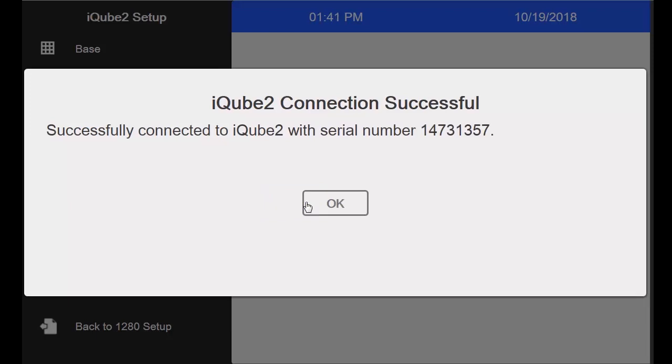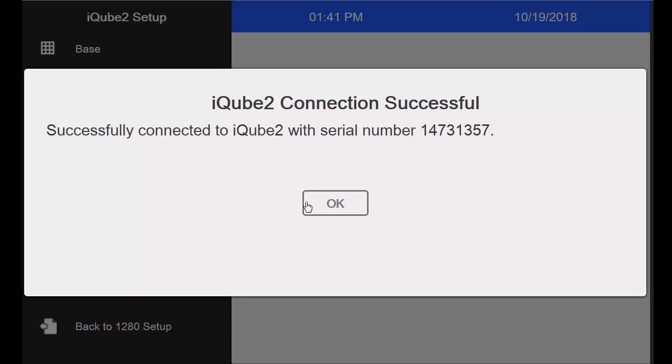As you can see here, my test was successful and returned the serial number of my primary board. If this test is unsuccessful, you will need to verify the settings in your indicator as well as your wiring. And depending upon your communication medium, you will need to check the iCube's dip switches as well. Since I have verified that my iCube 2 is talking to my indicator, I will press the OK button.